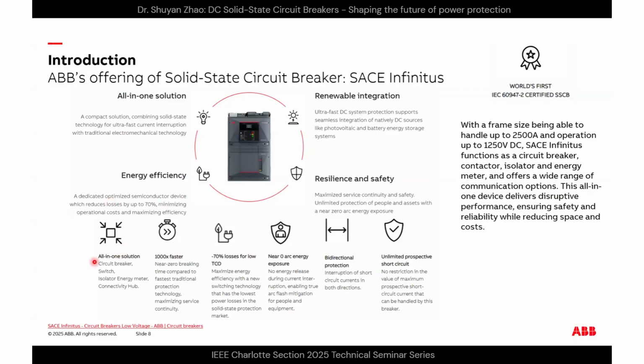There are a few features: an all-in-one solution, breaker, switch, isolator, and connectivity hub. It is 1,000 times faster, with near zero breaking time, like microseconds, compared to the fastest traditional protection technology like electromechanical breakers, maximizing service continuity. It has 70% less losses for low total cost of ownership. It maximizes energy efficiency with a new switching technology that has the lowest power losses in solid state protection. More importantly, it has near zero arc energy exposure, so there is no energy release during current interruption, enabling true arc flash mitigation for people and equipment.